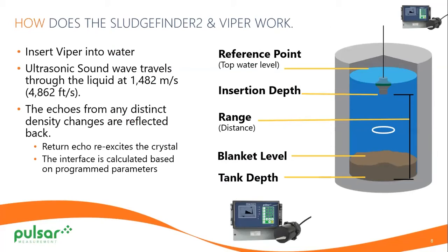Reference point is the top of the water. Insertion depth is the bottom of the sensor. Your range is from the sensor face to the bottom of the tank. You have your blanket level, which is the second yellow line from the bottom, and then you have your tank depth. That is what it would look like when you install the sensor into the drink and what you would be seeing on the bottom of the tank.